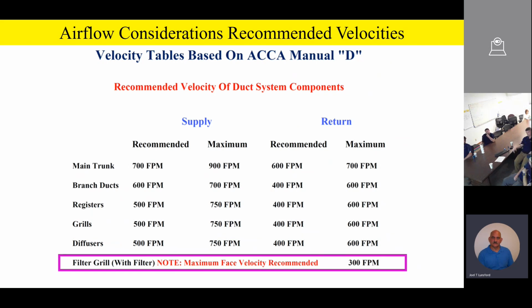One of the big things I like to remind everybody is that if you've got a filter grill, in other words, a return grill with a filter in it, you want to make sure you do not exceed 300 feet a minute across that filter. Another way of putting that is that if you've got real high velocity going across that filter, the filter is not going to work as well. In addition, it's going to be noisy and it's going to whistle. So please remember that if we have a return grill with a filter, we want to make sure it's plenty large enough to provide good filtration and not to exceed about 300 feet a minute velocity across the face of that filter.